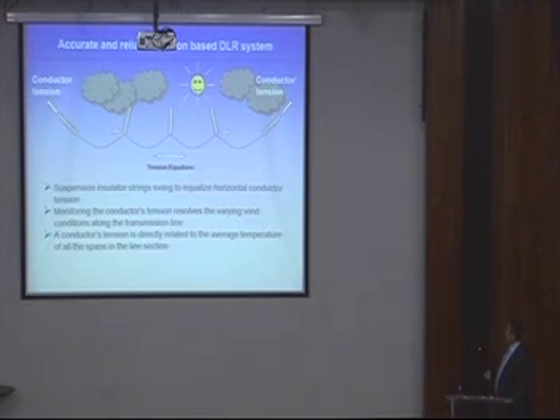So that means if something happens here, due to the equalization, the tension will change at the end of this section. So the tension measurement is a kind of integration of all the events, the weather conditions happening along the section. The same you could measure on the other side, but it's not necessary. In general, we are measuring the tension on one side and getting the information of all weather conditions in this area. And designers are designing a line exactly like that. They assume the average temperature causing a certain condition, and this behavior will be safe. So there will always be enough clearance in each of the single spans.